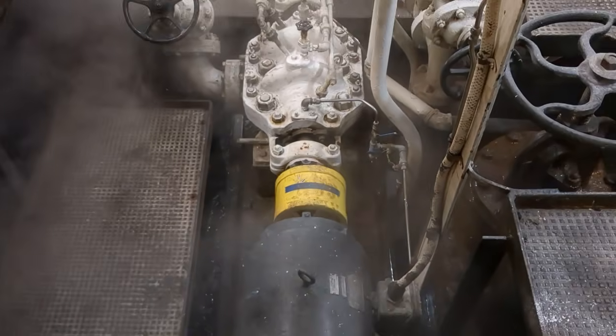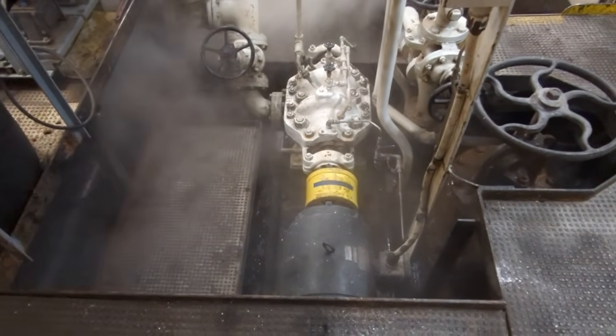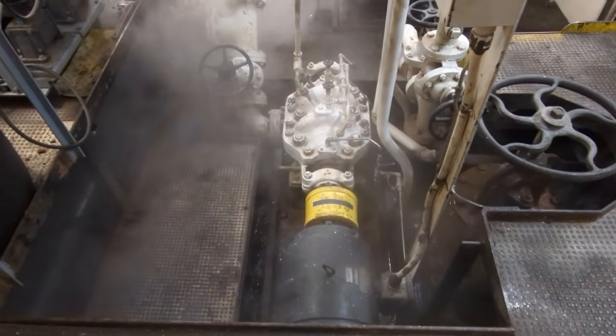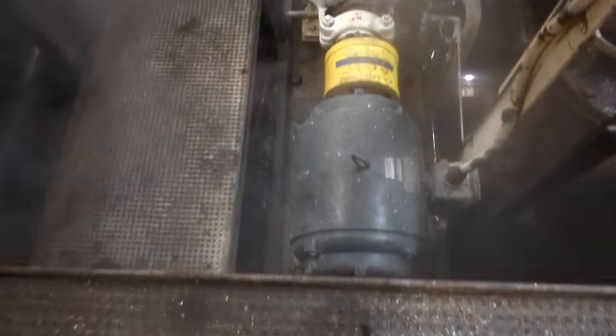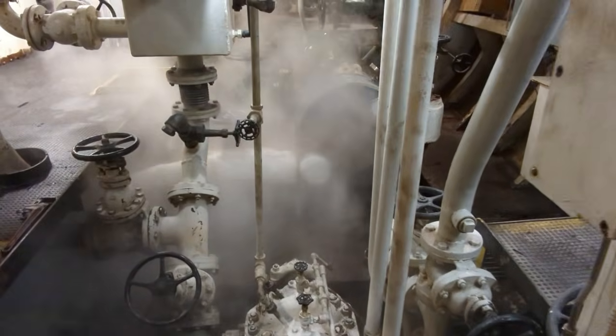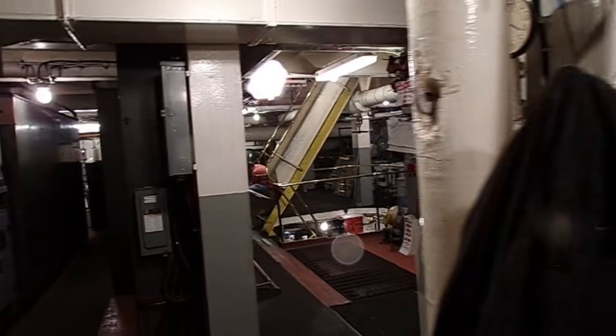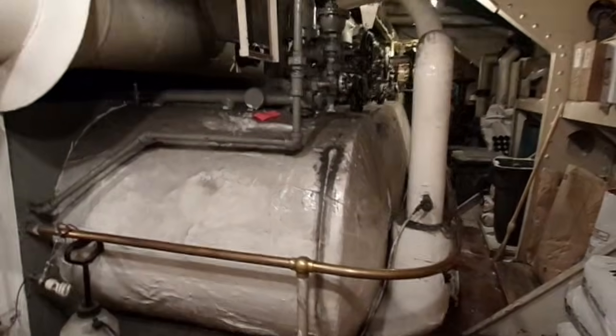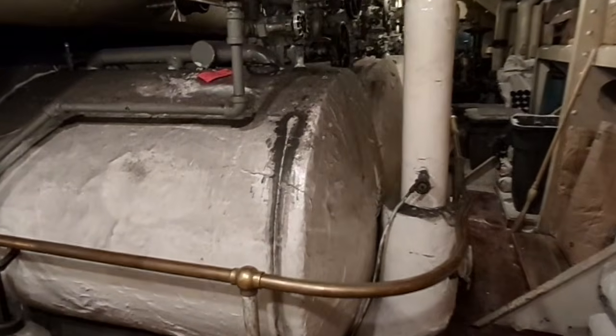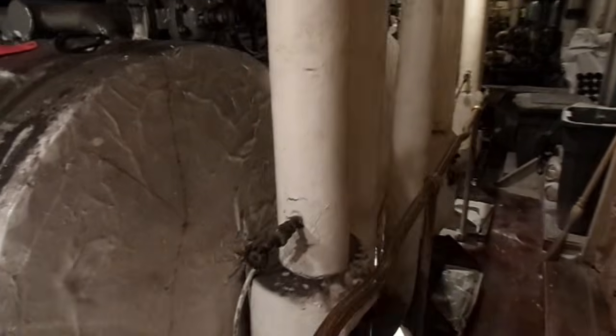As steam passes around the tubes and condenses, this electric pump removes the condensate from the hot well. Because the engine cylinders are lubricated with oil, small amounts can enter the exhaust steam. These filters remove oil from the water so that it won't clog up the boilers.